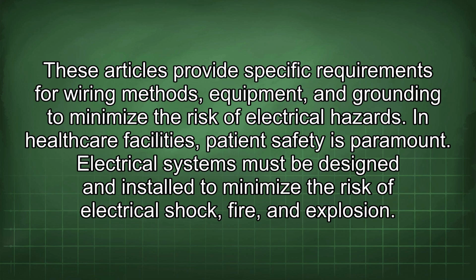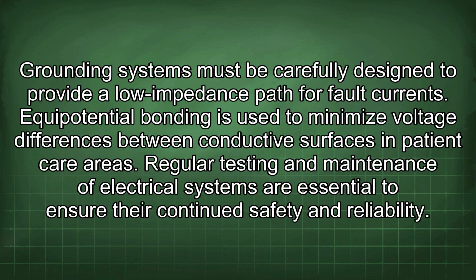In healthcare facilities, patient safety is paramount. Electrical systems must be designed and installed to minimize the risk of electrical shock, fire, and explosion. Grounding systems must be carefully designed to provide a low-impedance path for fault currents. Equipotential bonding is used to minimize voltage differences between conductive surfaces in patient care areas.